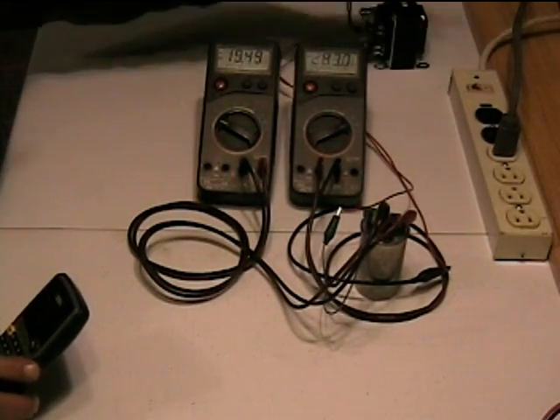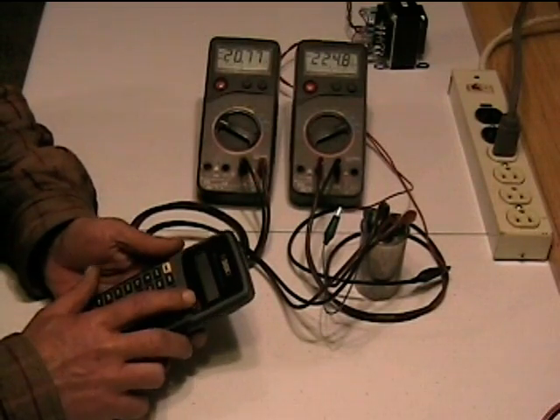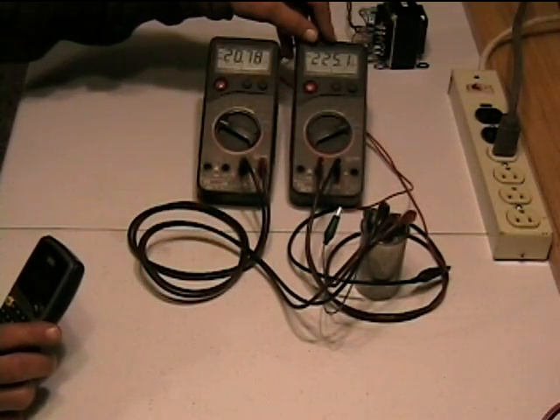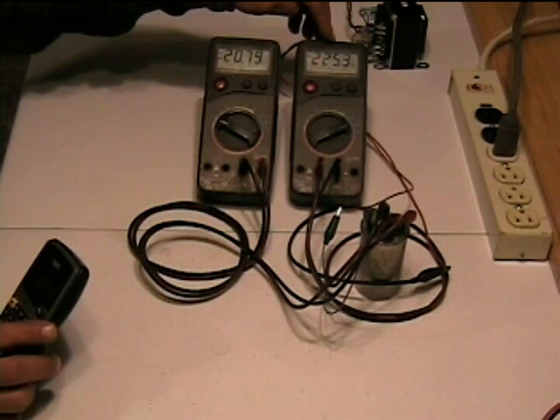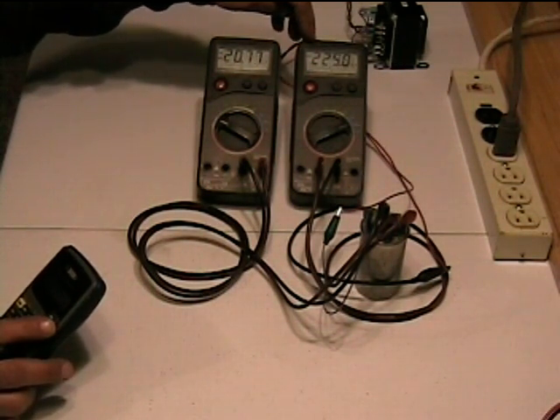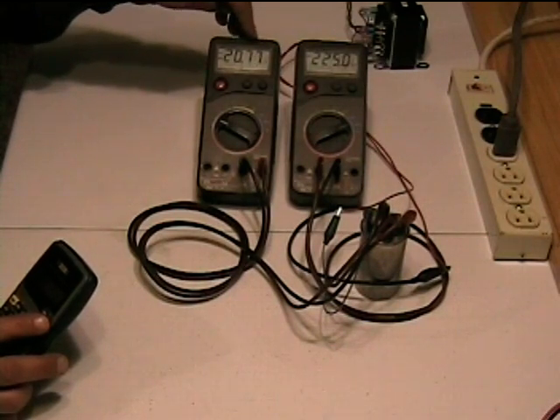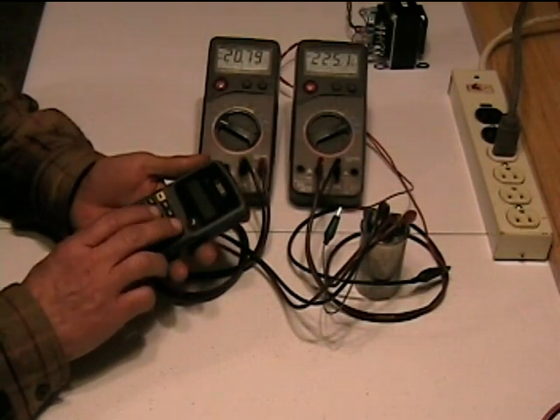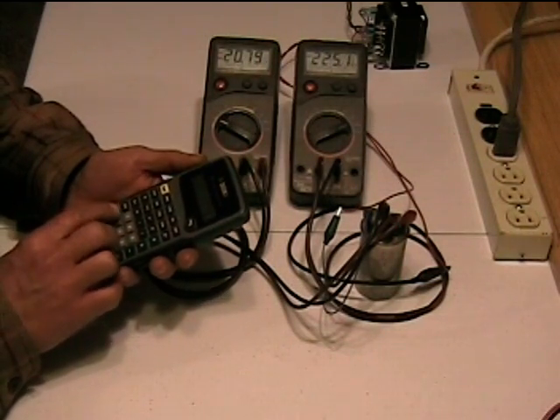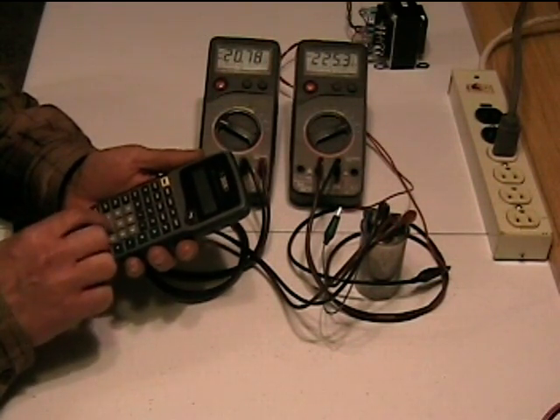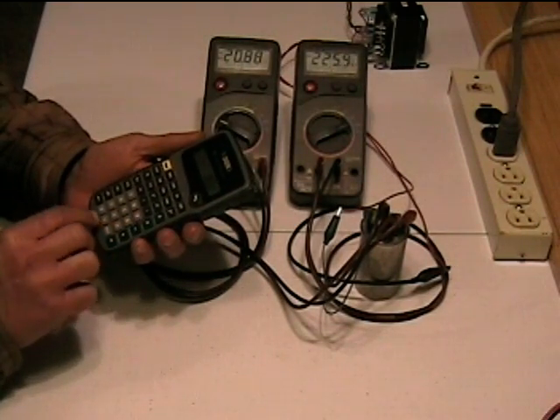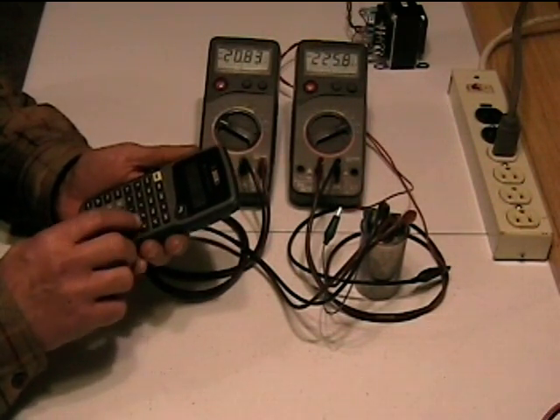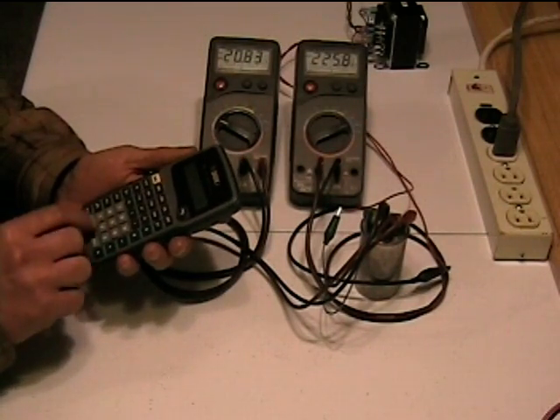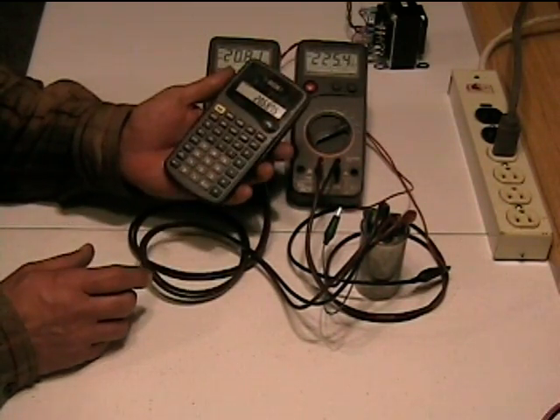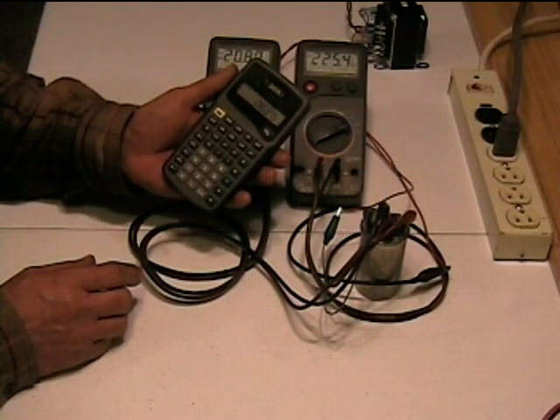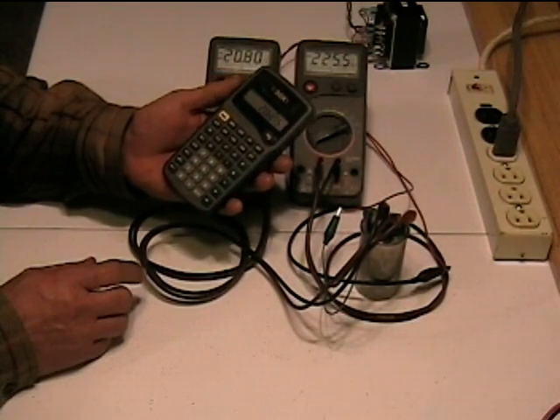Now this capacitor is small enough, the current is low enough, we can leave this on continuously. This meter is set up to read in milliamps. We've got about 225 milliamps, which would be 0.225 amps, and we're at 20.78 volts, about 20.8 volts. So we take our constant, 2652, multiply that times 0.225 amps, and divide that by the voltage, 20.8, and we get our answer of 28.68 microfarads, which is about what our electronic capacitor tester said that it was.